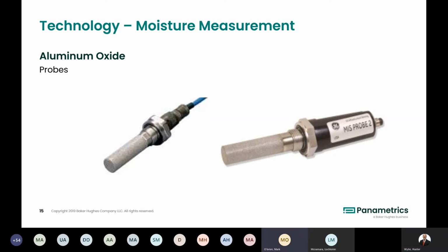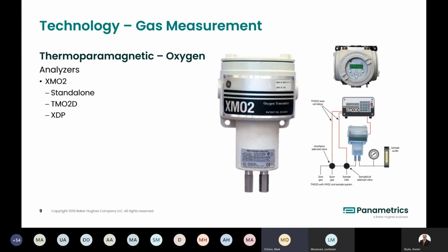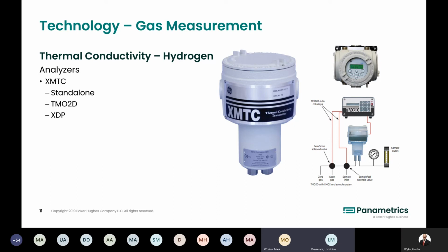Well, yeah, I suppose you've got two classes of failures with analyzers. One is a physical issue, where you have a blockage in your pipe, or your flow rate's too low or too high. And then the other side is the electrical side. So if the transmitter is either dead or giving an erratic reading, a lot of it comes down to training and education. If an XMO2, for example, is calibrated for use in a certain gas composition, and then that gas composition changes, because the customer's process changes over time, and now all of a sudden he's saying the analyzer is not reading correctly, it may be that the gas composition isn't the same as the unit was calibrated for at the beginning. So that's one thing. This is why we recommend periodic calibration on the XMO2 and the XMTC, just to make sure that your analyzer is always calibrated for the gas it's measuring.